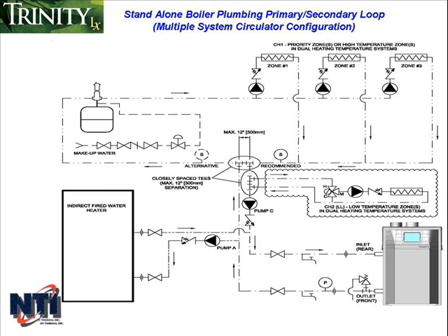During a central heating demand, the boiler energizes the central heating circulator through the central heat pump output, which is Pump C. During a domestic hot water demand, the boiler de-energizes Pump C and energizes the domestic hot water circulator, Pump A. So both Pump A and Pump C used in this configuration are responsible for water flow through the boiler and must be sized according to the minimum pump specifications for the primary pump laid out in the previous section. In this configuration, you don't use the output for Pump B because there isn't a dedicated primary pump or boiler pump that needs to come on with every call.